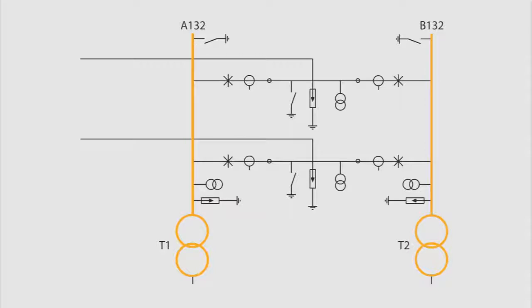In this particular case, 1 bus bar and transformer are taken out of service to enable maintenance of one of the disconnecting circuit breakers. Furthermore, if there also had been a disconnecting link between the bus bar and the disconnecting circuit breaker, a live removal from the bus bar could have been made. In this way, both the transformers and bus bars would be unaffected by maintenance.